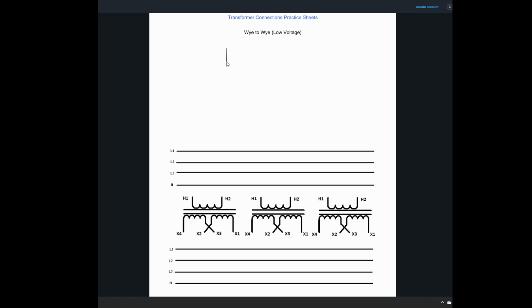So we're going to do our primary here. And again, if you've watched the other videos, then you can see that we're doing the primary on this side. Then we'll use this diagram in order to wire up the diagram below here. So with this guy, we're going to feed line 1 into this terminal right here. We're going to have line 2 coming into this guy, and then we'll have line 3 coming in here. Okay, these labels right here on our primary are going to be H1, H2, H1, H2.